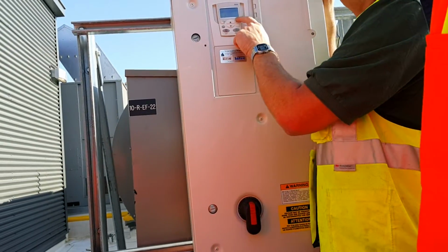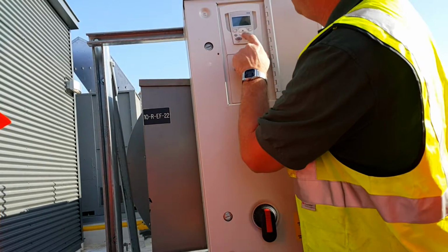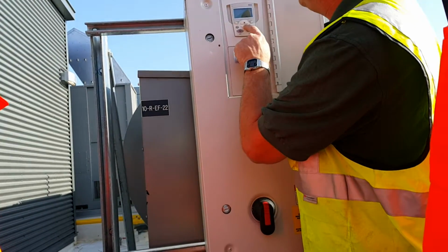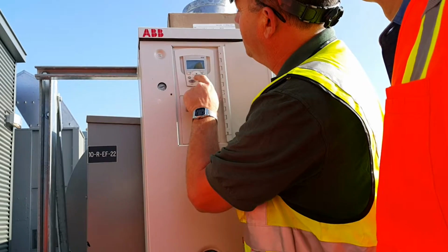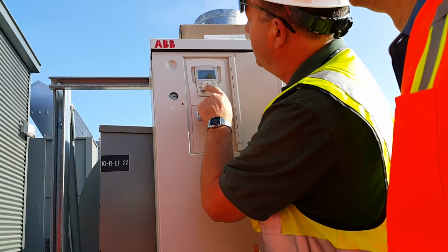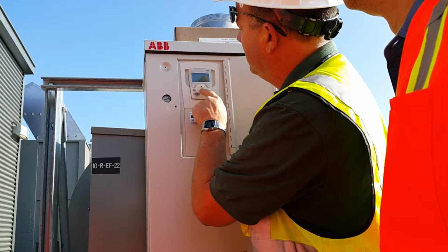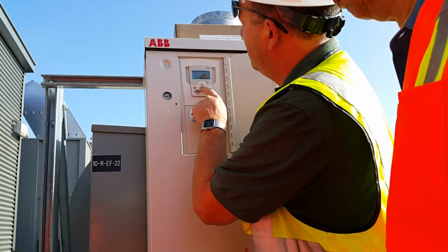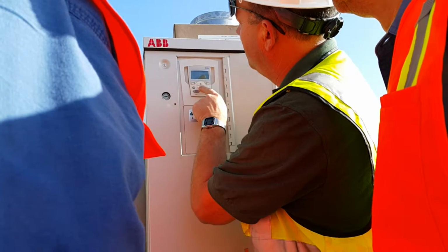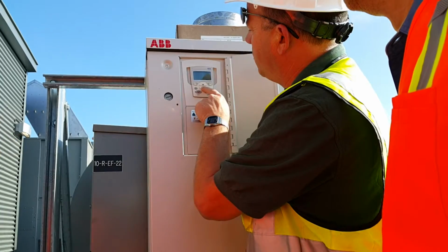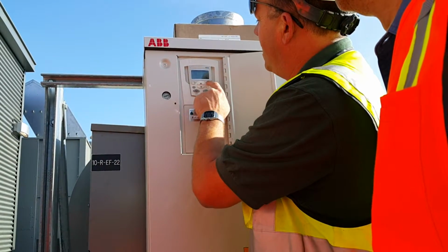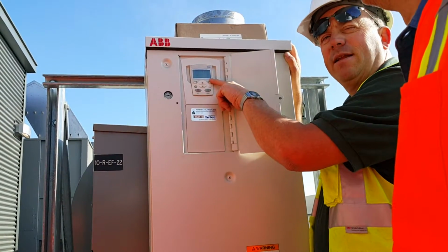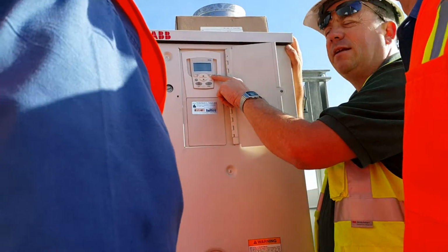And we can hit details. We can see what it was doing at the time it faulted. We can see the time, status, and most important, frequency was at 30.1 hertz. Speed was at 904. Torque was minus 0.6. Current was 2 amps. The DC bus voltage was 424 as it was dying off. And that's it. We can hit diagnostics right here. The soft key right above this is diagnostics.